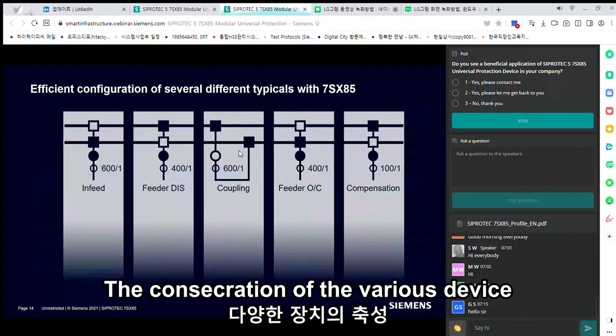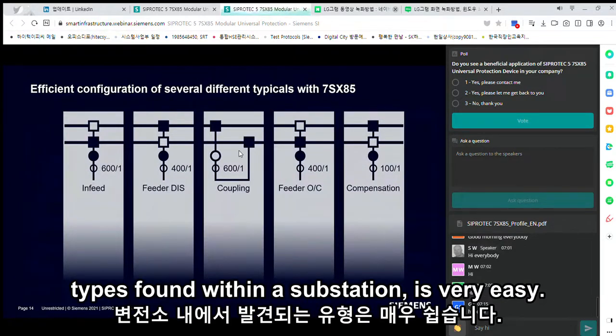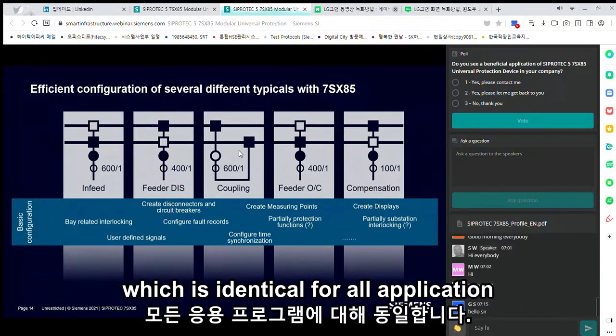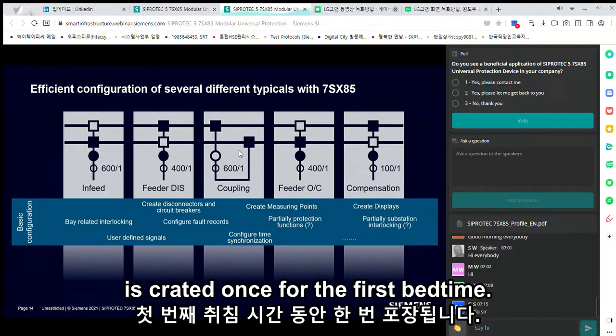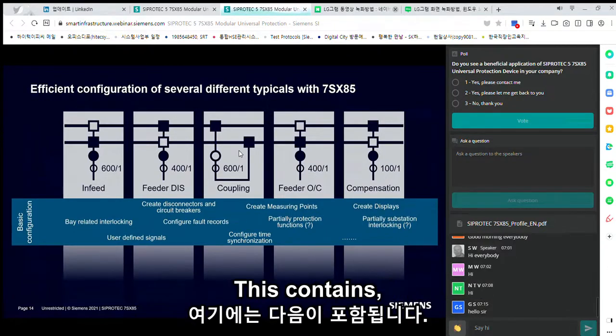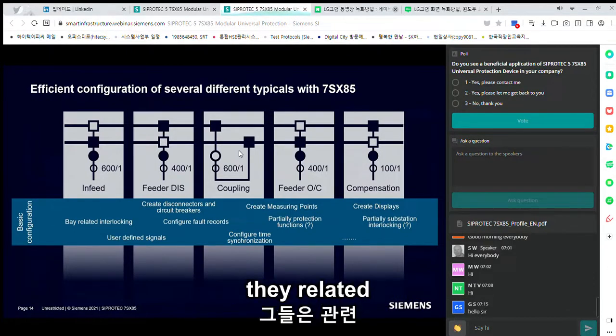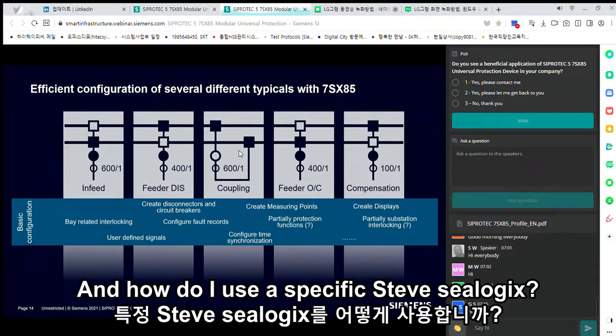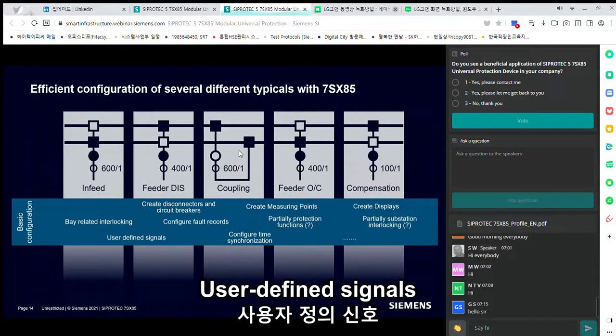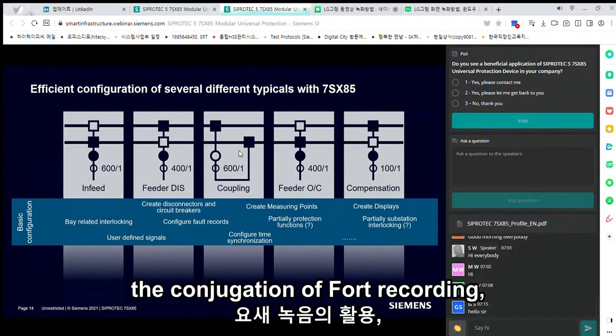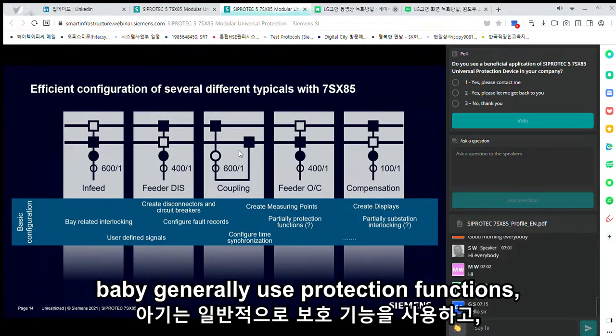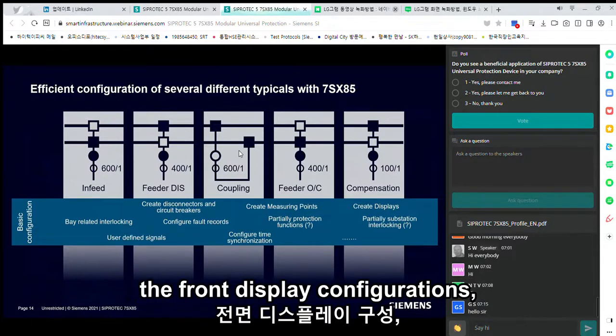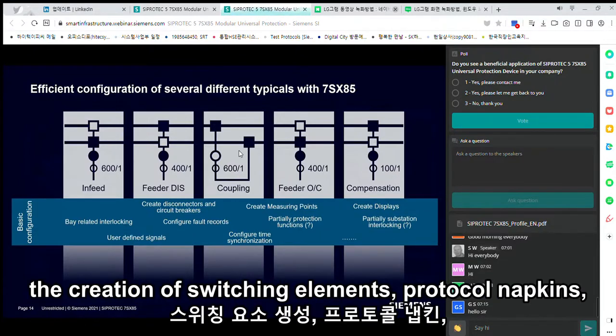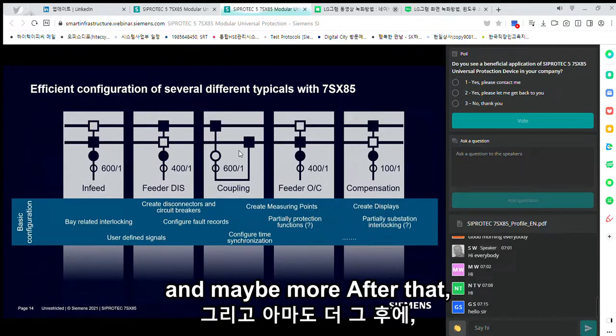The configuration of the various device types found within a substation is very easy. A basic configuration, which is identical for all applications, is created once for the first bay type. This contains, for example, bay-related interlockings and other user-specific CFC logics, user-defined signals, the configuration of fault recording, maybe generally used protection functions, the front display configurations, the creation of switching elements, protocol mappings, and maybe more.